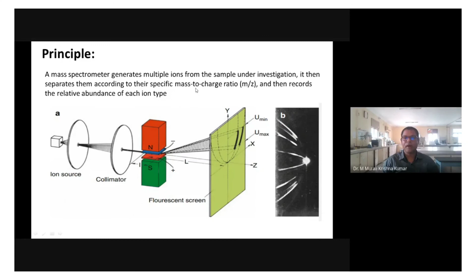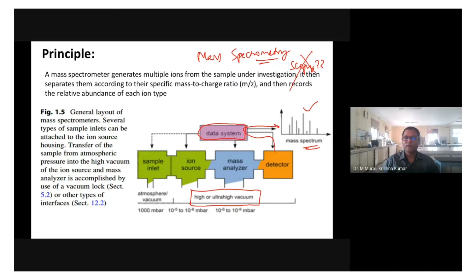So the general layout of a mass spectrometer is, we have 4 units. One is the sample inlet, the ion source or ionizer, the mass analyzer, and a detector. And this entire setup will be kept under very high vacuum. And then each one of these units is connected to a data system, so that whatever information we get from the detector is plotted as a mass spectrum. Okay, because we are getting things in lines, that's the reason why we call it spectrometry. Okay, mass spectrometry, but it is not spectroscopy. It is not spectroscopy, it is spectrometry.